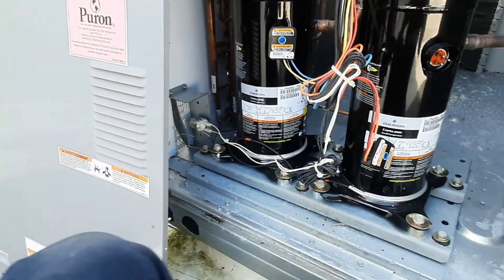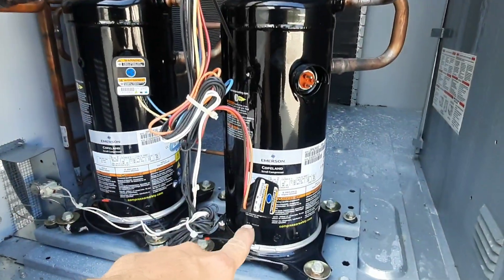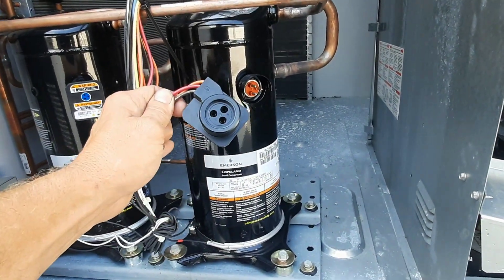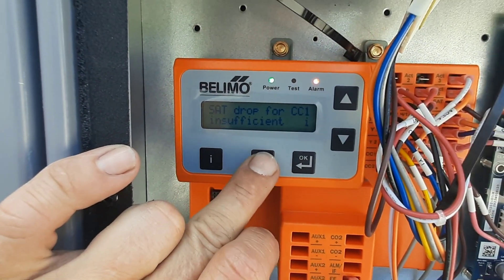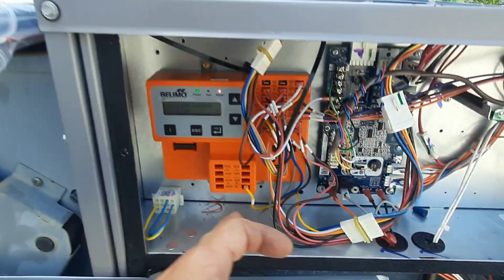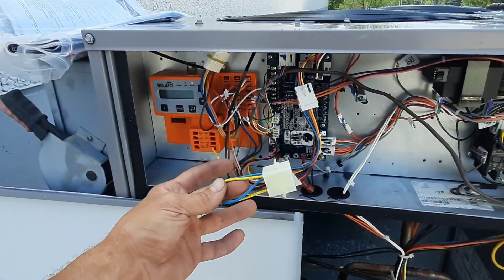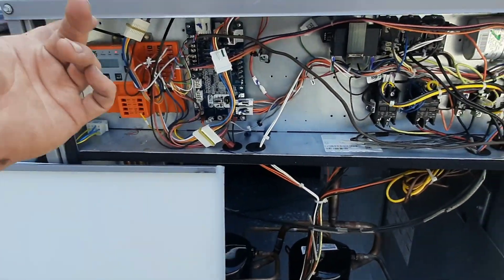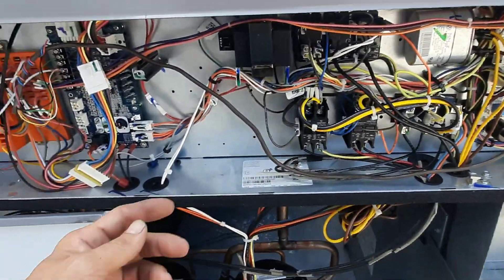Look at the diagram and see if we can find out what this stuff does. I just noticed that — cooling system problems. Supply air temp drop for CC1 insufficient. Okay, so that makes sense. I haven't dealt with these Belimos much. Somebody left a jumper. The cooling's not sufficient because it's not seeing a temp drop.